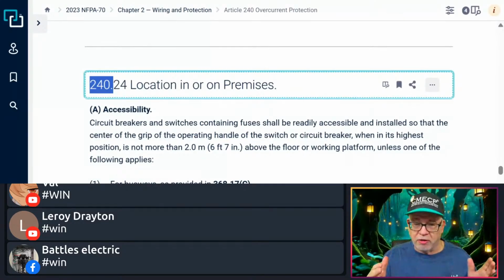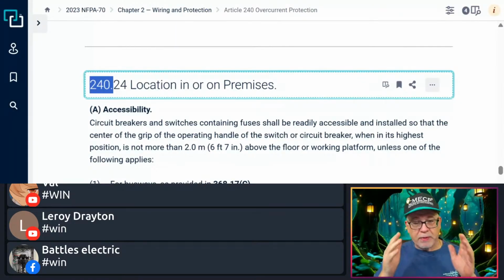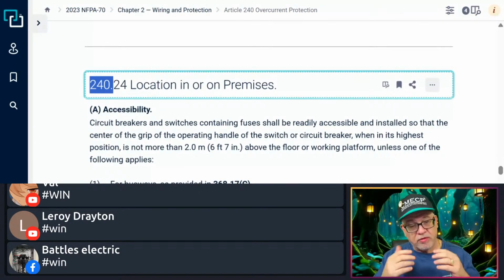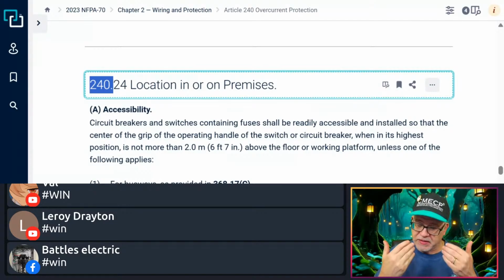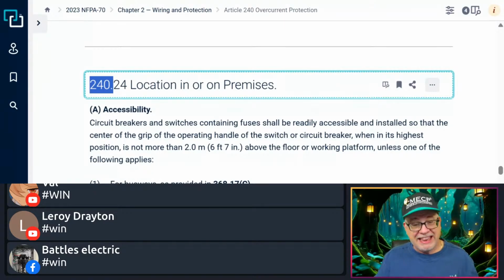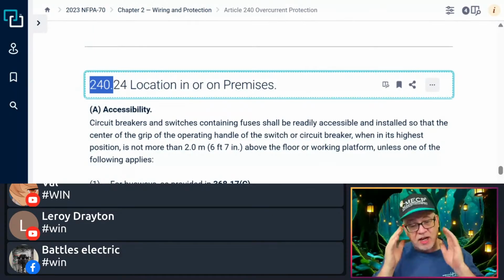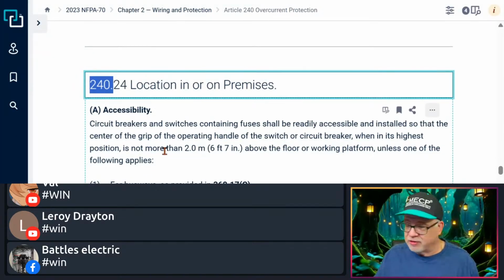That's either a load center, or a remote distribution panel, or a distribution panel, or service equipment, or a feeder panel. Okay, that's what that is. Panel boards are the guts that go in this equipment, in these cabinets, right? The circuit breaker or overcurrent device mounts onto the panel board, which is part of the guts that go in the cabinet or enclosure. That was golden right there. You should take that to the bank.